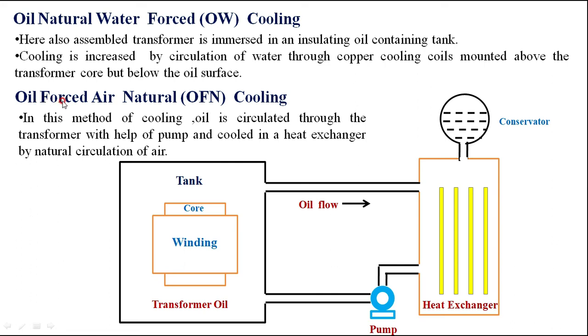The next method adopted is oil forced air natural cooling, that is OFAN cooling. In this method, oil is circulated through the transformer with the help of a pump and cooled in a heat exchanger by natural circulation of air. There is a separate heat exchanger unit and a pump. Instead of stagnant transformer oil, the oil is sucked using the pump, circulated through the heat exchanger where the heat is dissipated, and then the cooled transformer oil is returned to the transformer tank.